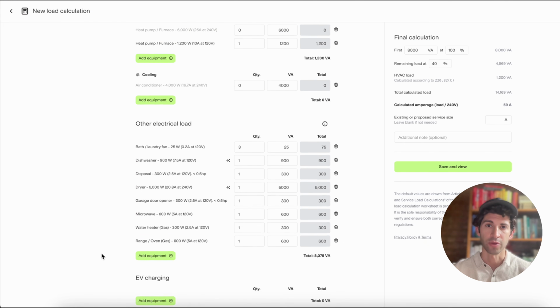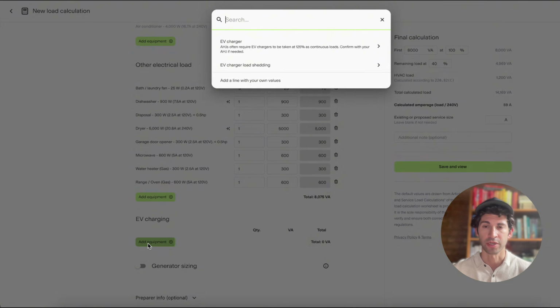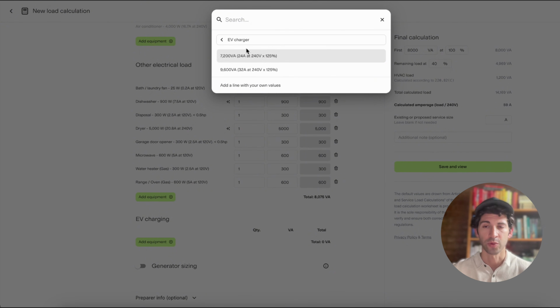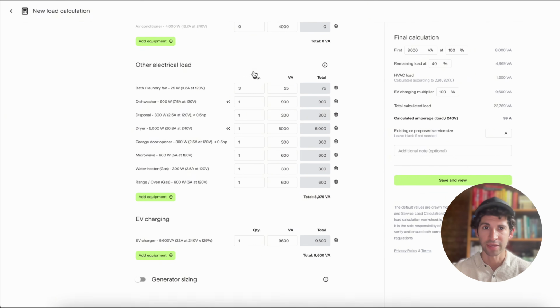Now it's time to add in that new EV charger. This EV charger is rated to charge at 32 amps and 240 volts. Since this AHJ expects to see this at 125%, we select 9,600 VA.